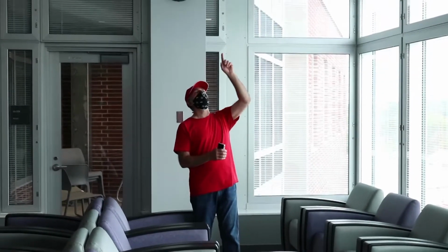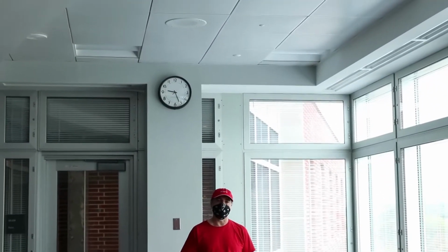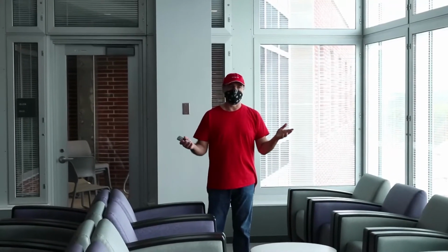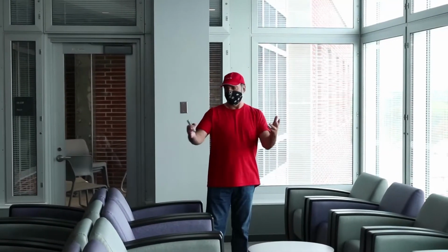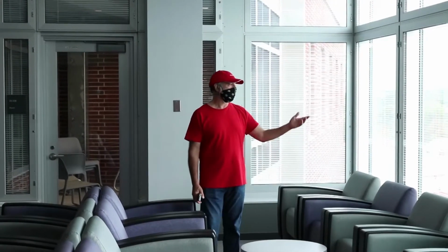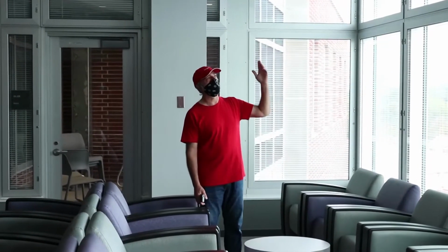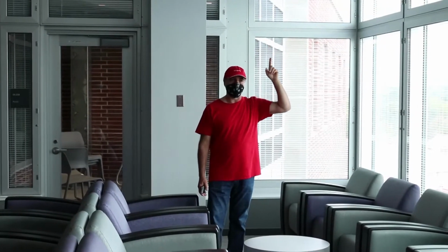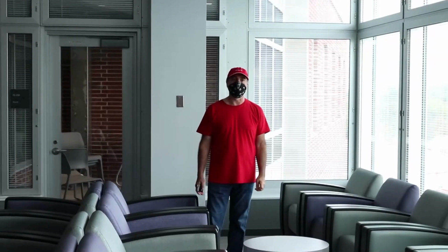Okay. A little troubleshooting hint: if this becomes a problem, this isn't the official way to do it, but you can put a piece of tape over that sensor, and then it will think it's darker than it really is, and the lights will come on if there's a complaint that this area is just too dark. Same thing, if you close the blinds, then this will also feel that it's too dark in here, and will also raise the light.